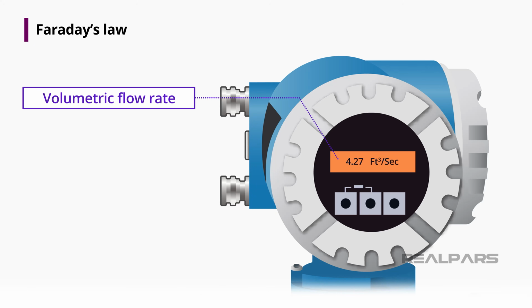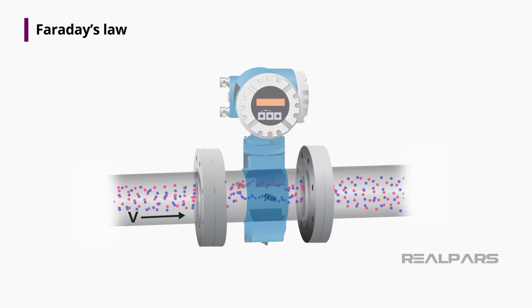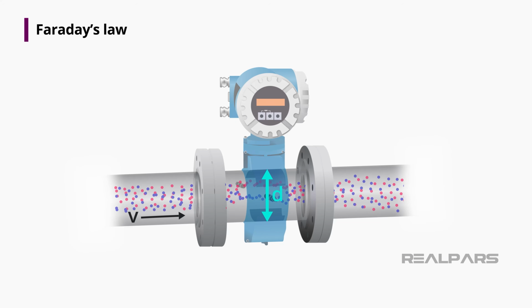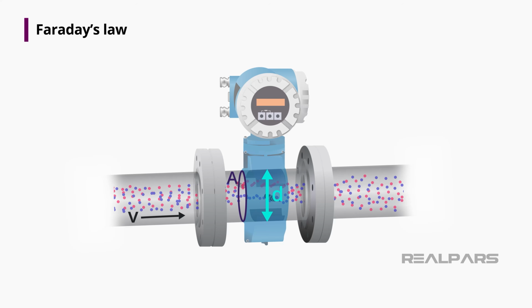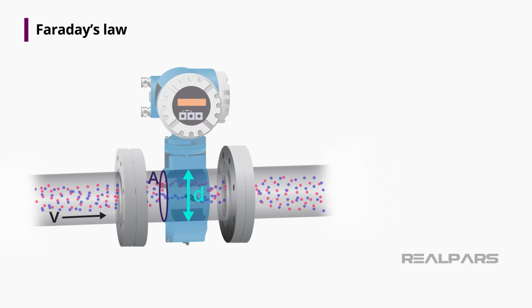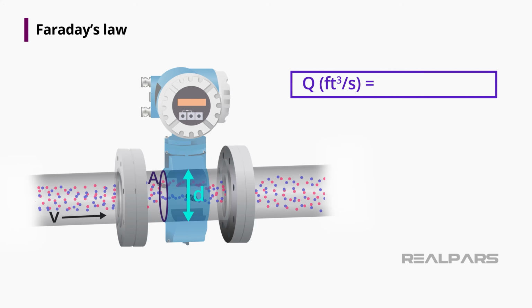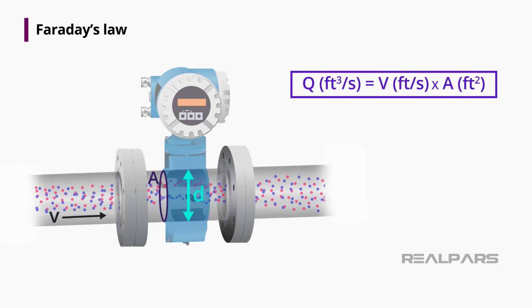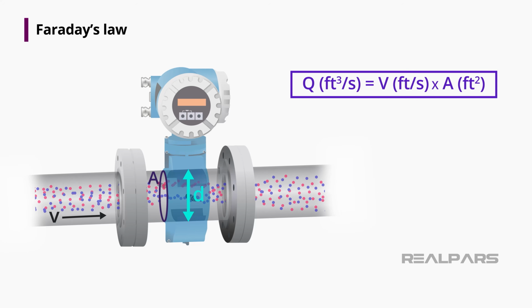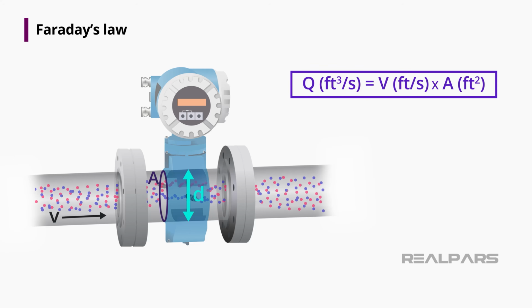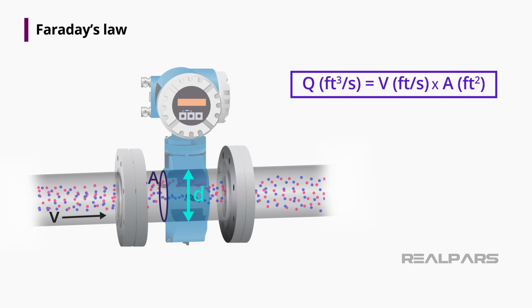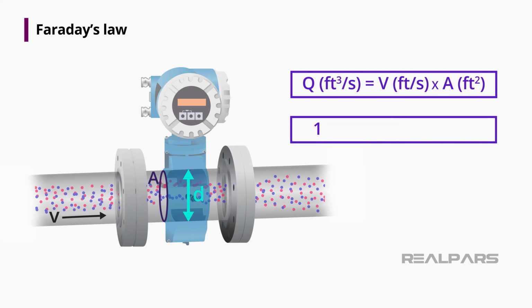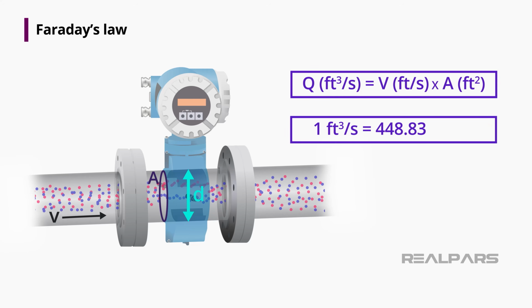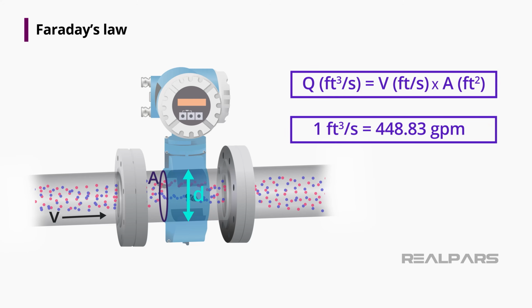The transmitter outputs a volumetric flow rate. The meter measures the flow velocity. The cross-section diameter, and hence cross-sectional area, is constant. So the resulting measured value of velocity in feet per second, multiplied by the constant area in square feet, gives a volumetric flow rate of cubic feet per second. This quantity can be scaled to any volumetric flow unit, such as gallons per minute.